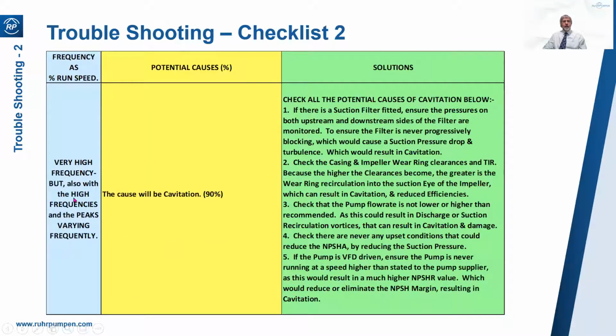Very high frequency and with peaks varying frequently, 90% of the time it's cavitation. You're also going to have that distinctive noise. Here are all the steps to take. So that's the crib sheet, vibration analysis for dummies.